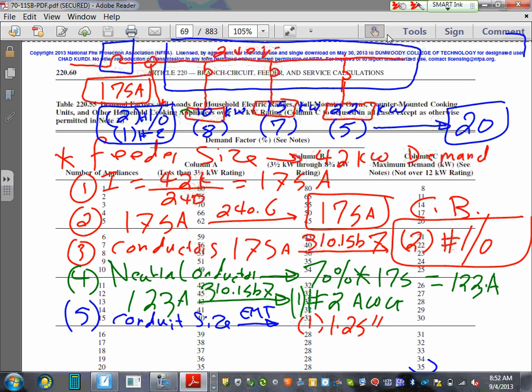1.25 inches EMT. In your case, guys, I don't want to go through the whole calculation. You know how to do the calculation that we did yesterday. You're going to go to Table 4, Table 5, add the square inches of all the conductors, then go from Table 5, then go to Table 4 and size your EMT conduit. Done. That's what you do. Is that what we designers do?